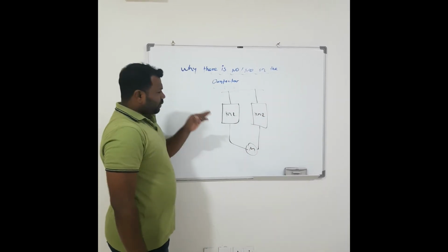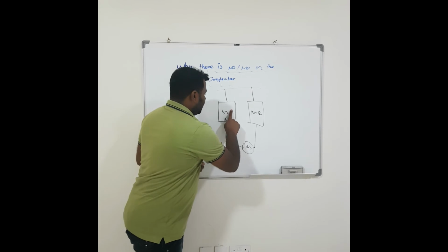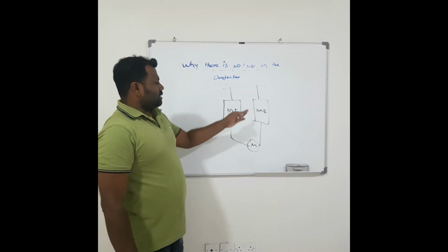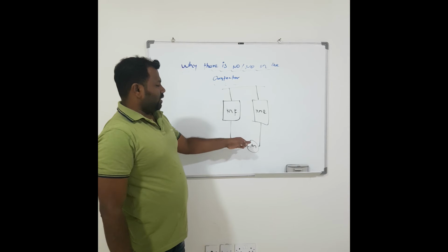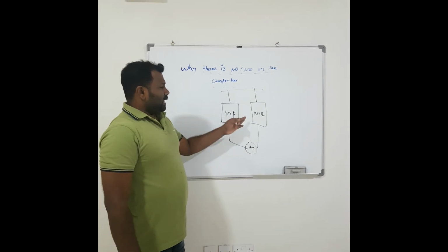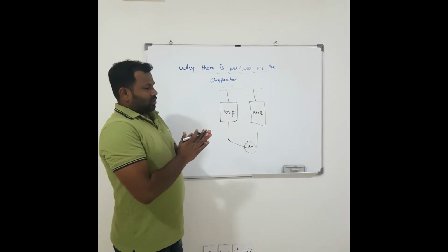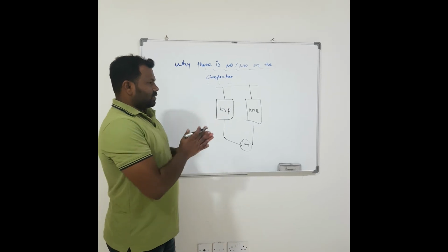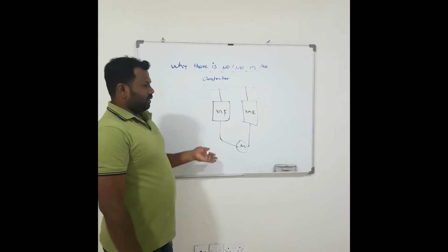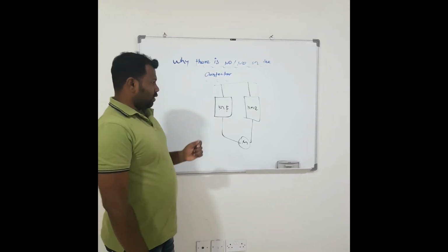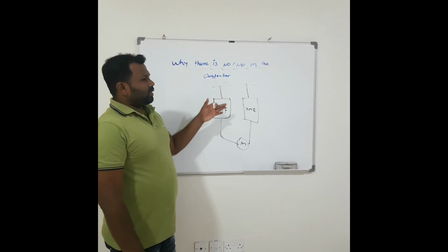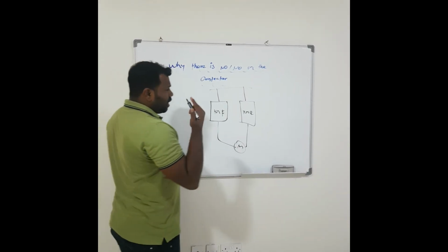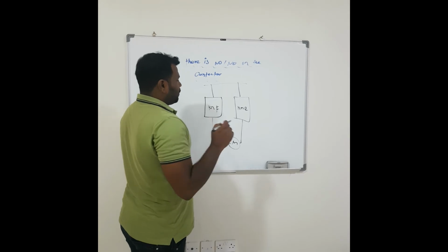Okay. Once this forward contactor closes, the motor will run forward. Once this reverse contactor closes, the motor will run reverse. Okay. But at the same time, both the contactors should not close. Once both the contactors close together, it will get short circuited. It will damage your motor as well as the other equipment also. So these contactors must be wired with an electrical interlock. Okay. So with this NC contact, it is possible.